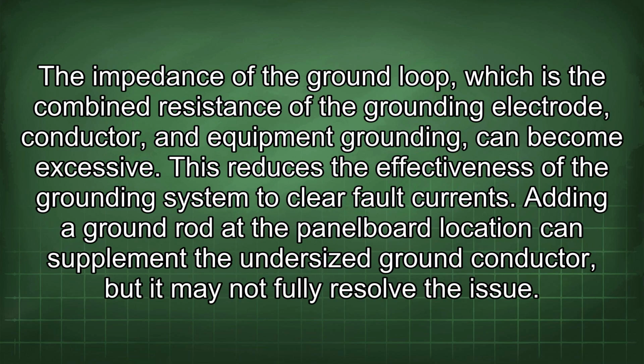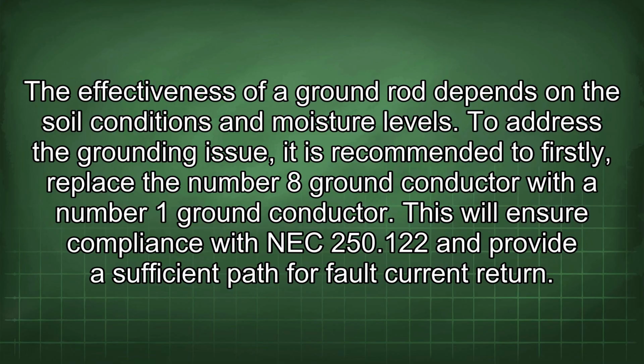The impedance of the ground loop, which is the combined resistance of the grounding electrode, conductor, and equipment grounding, can become excessive. This reduces the effectiveness of the grounding system to clear fault currents. Adding a ground rod at the panel board location can supplement the undersized ground conductor, but it may not fully resolve the issue. The effectiveness of a ground rod depends on the soil conditions and moisture levels.